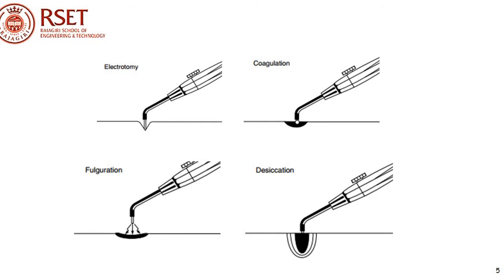When the electrode is held near the tissue without touching it, an electric arc is produced whose heat dries out the tissue. In desiccation, needle point electrodes are stuck into the tissue and then kept steady. Depending upon the intensity and duration of the current, a high local increase in heat will be obtained. The tissue changes due to drying and limited coagulation.